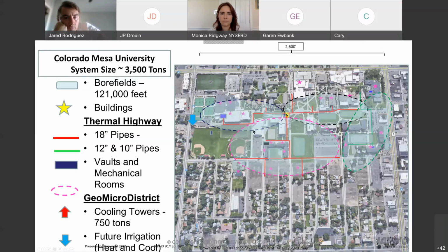So this is a dynamic and growing process, it doesn't have to be static. As of yesterday we now have 4 cooling towers, with a total of about 1,200 tons of cooling capacity to shed heat. We've got about 200,000 vertical feet of bore field spaced across the campus, so we have thermal storage and our primary heat rejectors. This system has boilers attached, but nothing in this system has had to initiate a boiler fire for the last 13 years, other than some domestic hot water topping that we're doing. We'll talk about that later.